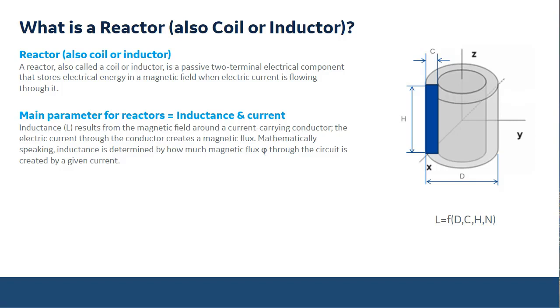So if there is current flowing through this coil reactor, this current creates a magnetic field, and this magnetic field is a reaction of that current flowing through the conductive material that I mentioned. So when we're talking about reactors, the magnetic field will be one of the most important aspects of the design. The magnetic field depends basically on how much current flows through the reactor, and also depends on the inductance or the impedance of this reactor. The inductance or impedance of the reactor depends on how many turns there are inside of that coil. What is a turn? Then comes the next question.